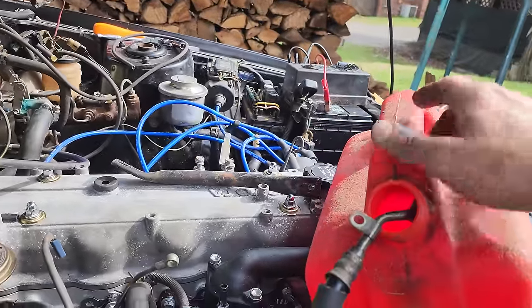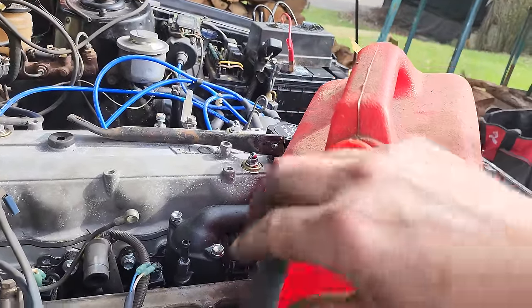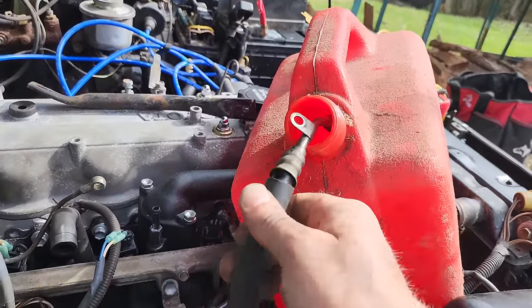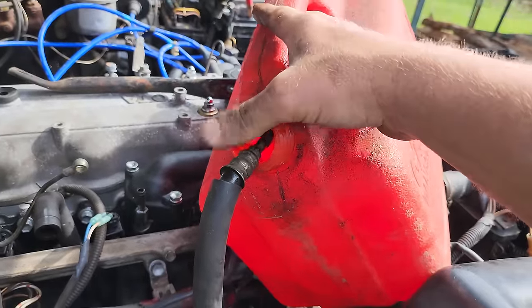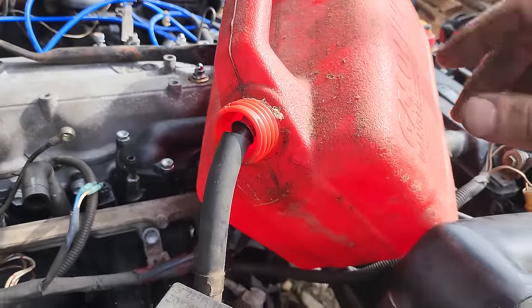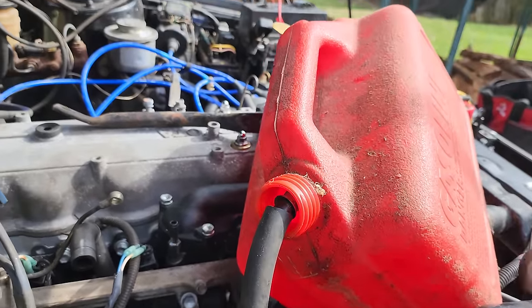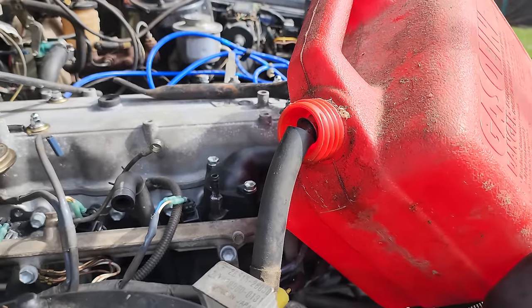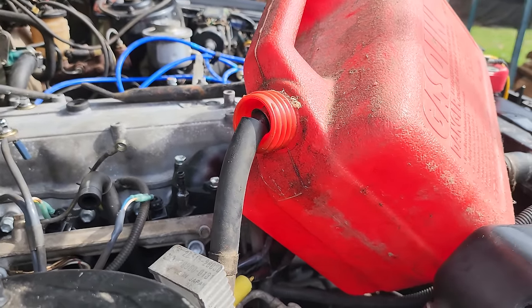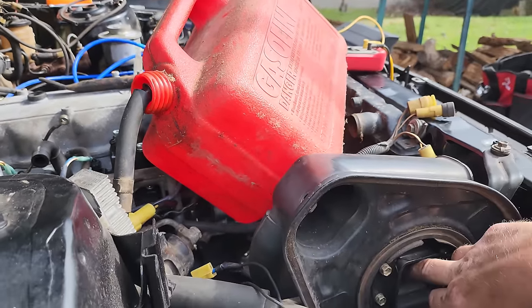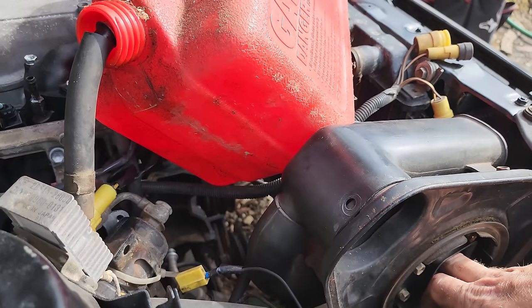Amperage too, I was a little misleading on those measurements because in this test everything's open, so there's no buildup of pressure since the line's open. Your amperage is definitely gonna be lower just from that alone. But we could still have a bad pump here. Let's get some more gas in it first and see.